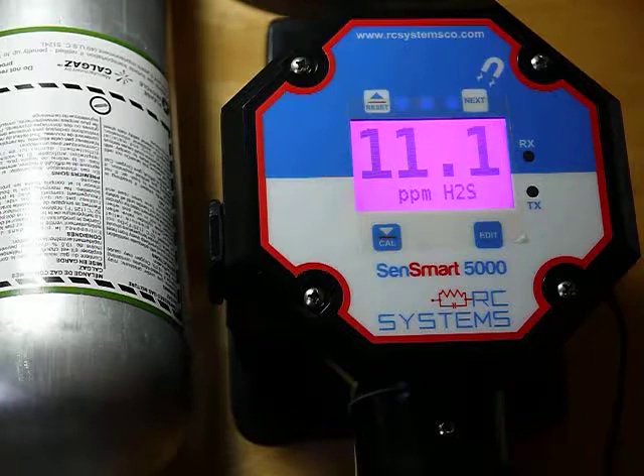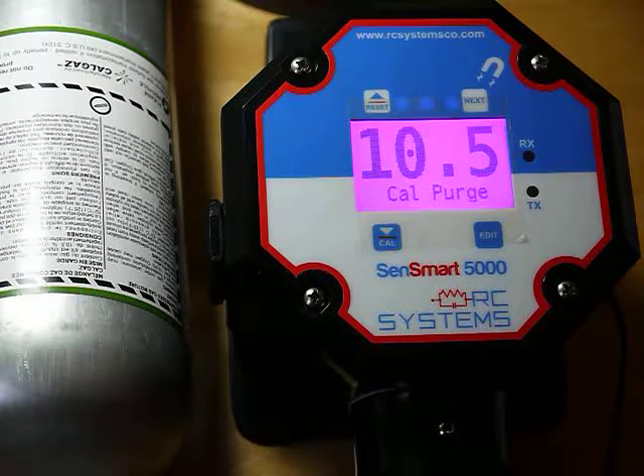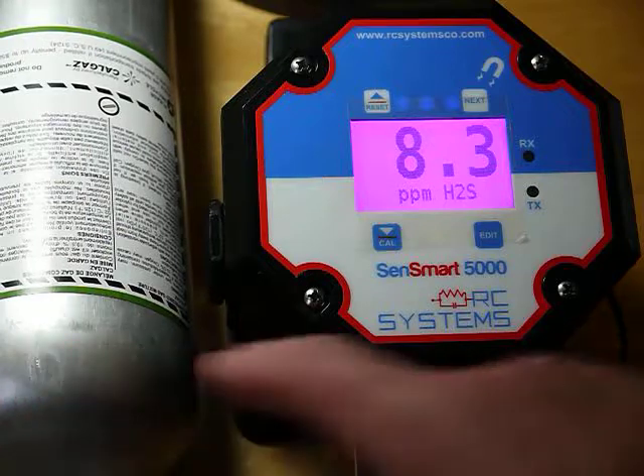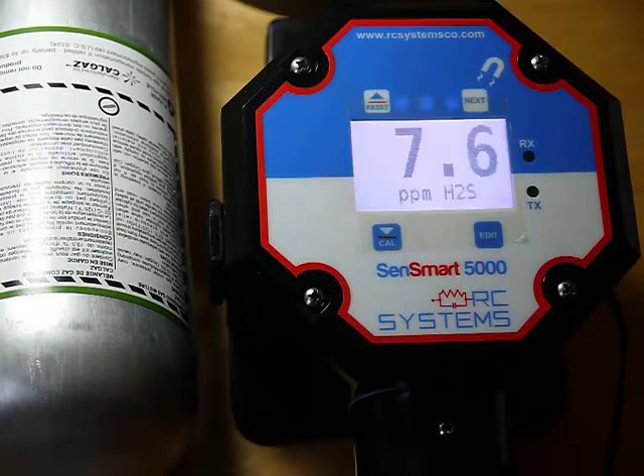Again, there's a bump test. A bump test is where you put gas on the transmitter and you're just looking for a steady 0 in clean air, and then you apply the gas from the cylinder. You look on the cylinder to see what the concentration is, and it should match what's on the transmitter, but there is no electronic adjustment done.